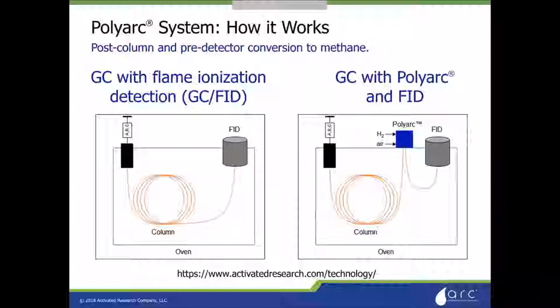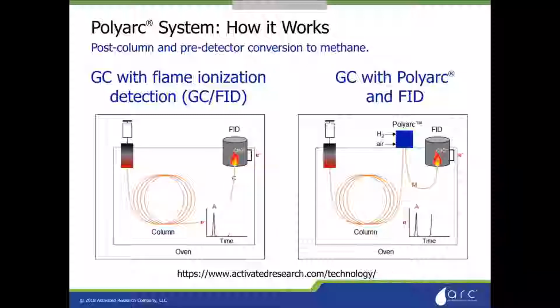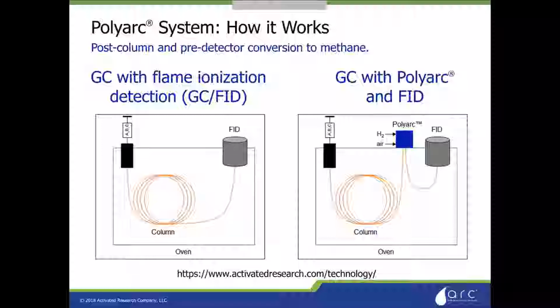How it works is actually pretty simple. You inject your analytes, you separate them through your column of choice, and instead of going directly to your FID, your detector, you go right into your PolyArc reactor. We add air and hydrogen to do a sequential combustion and then reduction. So all of your analytes, it could be benzene, gets combusted: a single molecule of benzene would get combusted to 6 molecules of CO2. And then those 6 molecules of CO2 would get reduced with hydrogen to 6 molecules of methane. And in your FID, you would measure 6 molecules of methane.